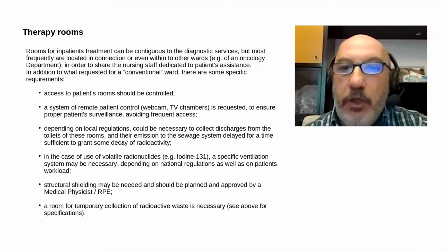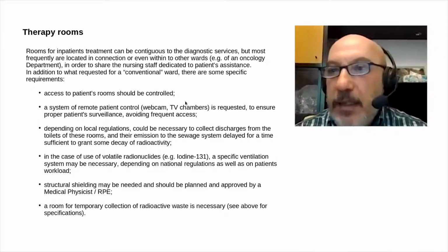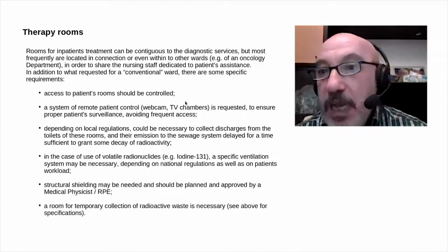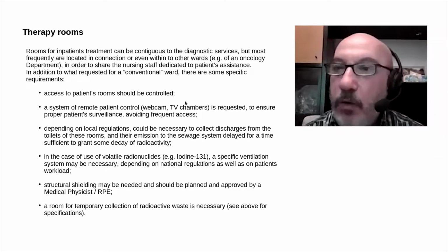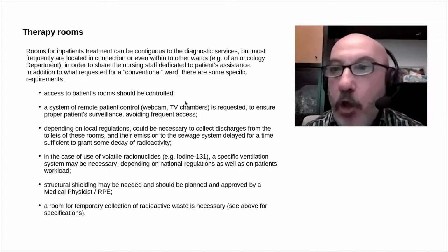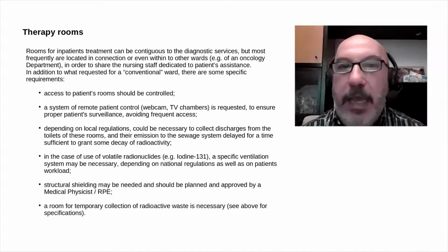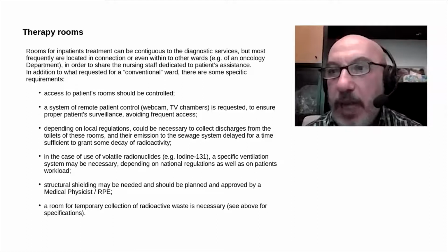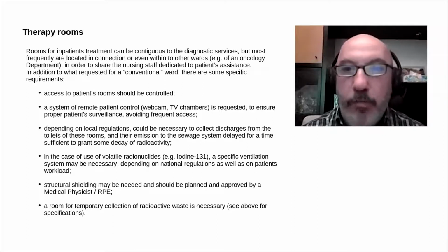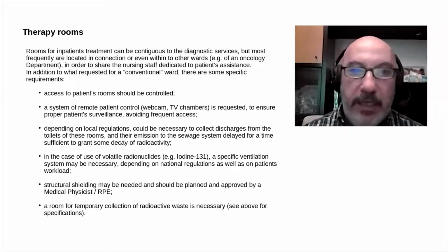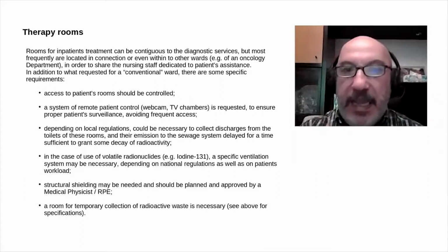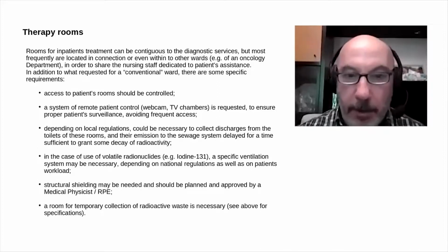Depending on local regulation, it could be necessary to collect the discharges from the rooms. There is not an international standard about this, and it has to be noted that the IAEA does not recommend the installation of waste collection tanks. What should be respected in any country is the clearance level for wastes after they are released into the environment.